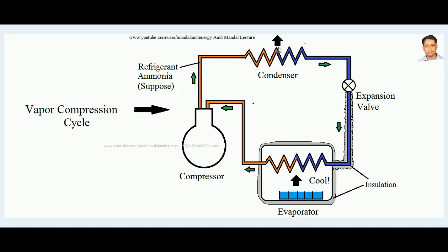In the condenser, the ammonia loses its latent heat to the atmosphere and becomes liquid. The refrigerant enters the condenser in vapor phase and, passing through it, ultimately becomes liquid by losing the latent heat of vaporization. This compressed refrigerant then passes through the expansion valve, where pressure reduces, and the ammonia reaches the evaporator.